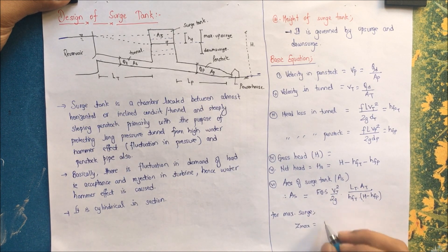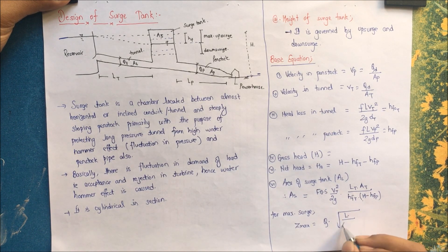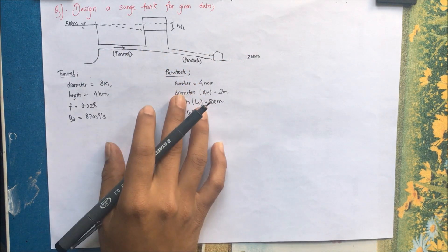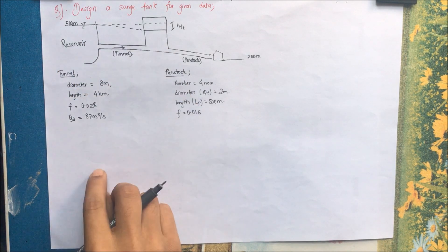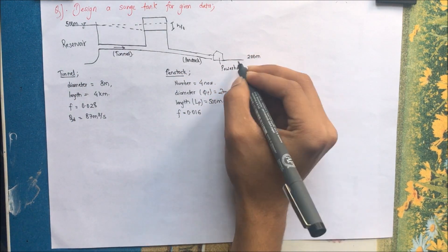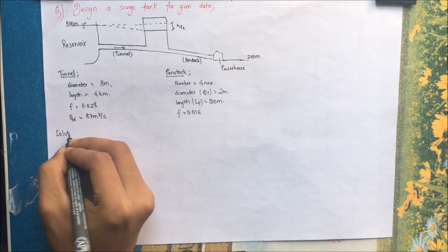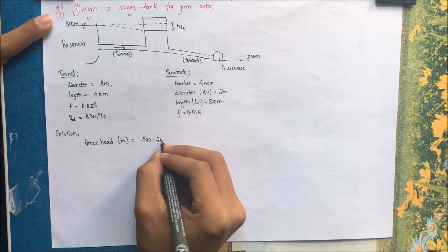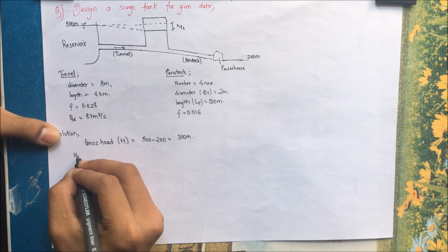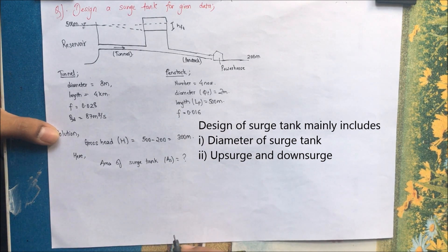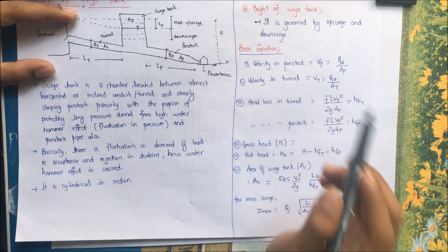Let us design a surge tank for the given data. The reservoir RL is 500 m and the powerhouse tailrace RL is 200 m. Solution: the gross head H = 500 − 200 = 300 m. We need to find the area of surge tank As. As already discussed in the introduction, we need to find various terms — let us go in sequence.